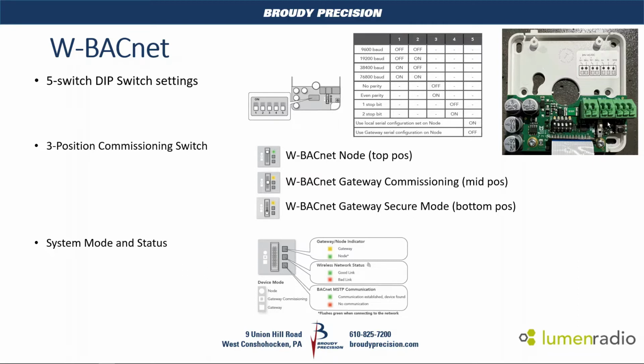There's also, to the right of the switch, to the left of the push button, 3 very bright LEDs. The top one is the indicator for whether it's a gateway or a node. Amber is gateway, green is node. The second LED is the wireless network signal strength status. Green is good link, red is a bad link. And then the third LED, the bottom LED, green is that communication is established and that the device is found, and red would be no communications.